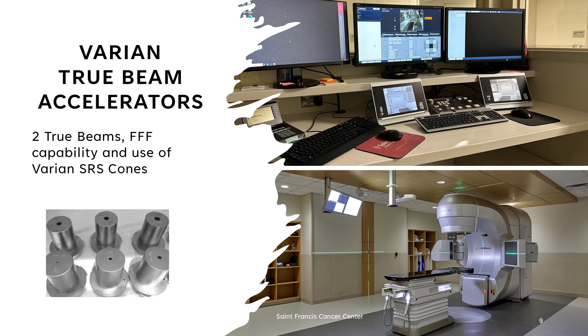In addition to farmer chambers, scanning microchambers, and diodes used in commissioning and annual work, the St. Francis Cancer Center uses Daily QA3 integrated into a common database from the SunCheck software. St. Francis Cancer Center routinely uses TG142 imaging phantoms for kV and MV image quality testing, in addition to the vendor-supplied CATphan, patient in vivo dosimetry with the microSTAR OSLD nanoDots, and the SNC 3D dosimetry round tank and 1D tank with PC electrometer.